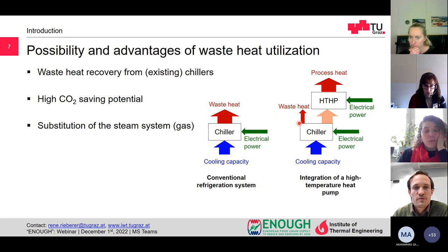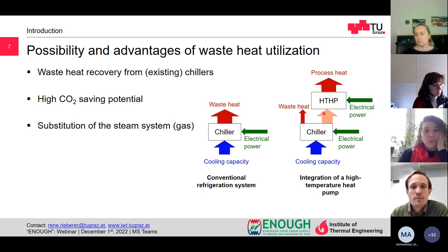So parts of the waste heat or the whole waste heat can be used as a low temperature heat source for the heat pump, and can be lifted up to a temperature level suitable for this process heat supply. This can save CO2 emissions, and also steam systems or hot water systems can be substituted, which are normally driven by natural gas.